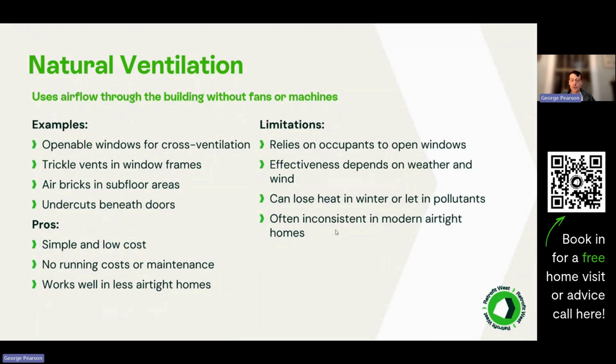maintaining a dry underfloor. In homes that have been retrofitted with insulation and air tightness improvements, natural ventilation alone often becomes insufficient. The reduced air leakage means less unintended air exchange, so moisture from cooking, showering and drying clothes can build up more quickly.